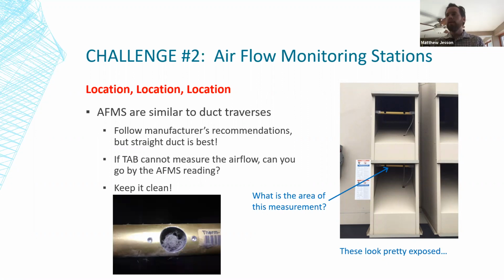Also, they have to be kept clean. Most of these airflow stations, this particular type that's shown, operate similar to a hot wire anemometer. They operate on thermal dispersion. As the airflow goes through, it cools an element, and that provides you your velocity. If they get dirty, that kind of acts as an insulation around that element, and it'll read falsely low. And this is something that we have encountered many times. If these airflow stations are being used in a building pressure control sequence, if you're determining how much air to exhaust based on how much outdoor air you have, this can throw your building out of whack in a hurry.